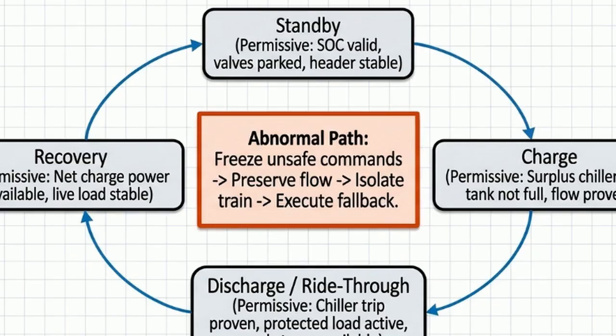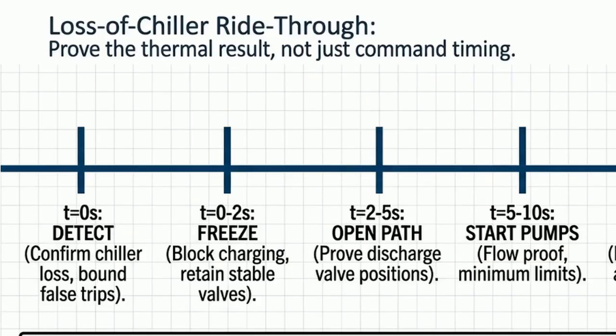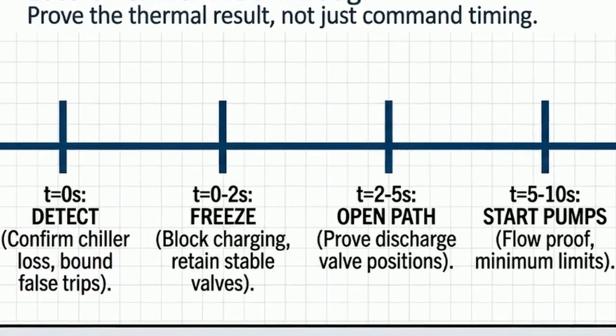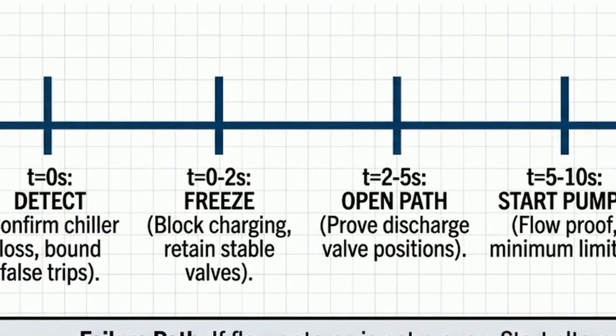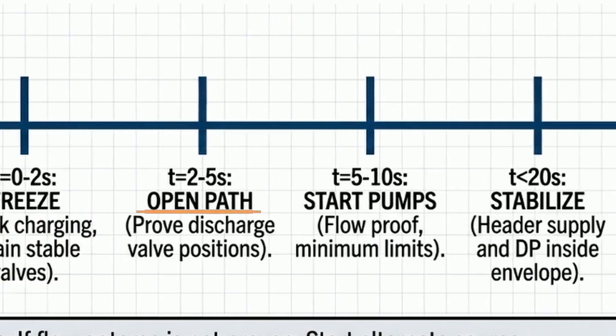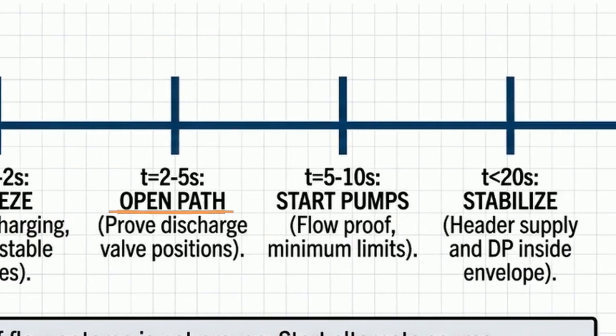Looking at the exact chronological sequence of a loss of chiller event, the ride-through timeline begins precisely at T0, when the system detects the failure and bounds any false trips. Within the first 2 seconds, the system enters the freeze stage. It explicitly blocks any charging commands and latches the valves in place to prevent hydraulic disruption. By second 5, it begins opening the discharge path, and by second 10, the pumps start.